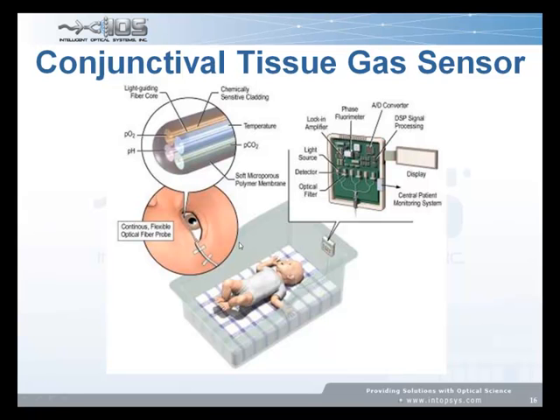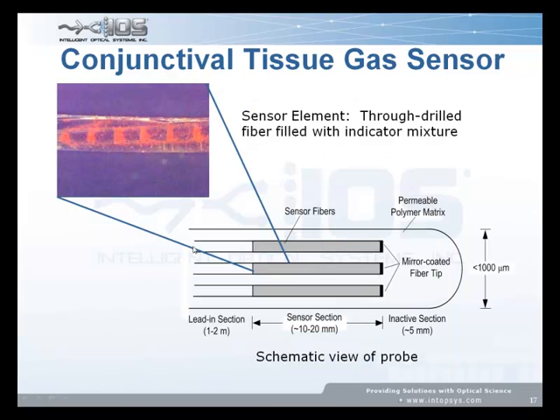We found that yes, they blink a lot, but you don't have to stick them with needles. By putting this probe in here, you can wind up making a very good real-time online measurement. You want to make it as small as you can. So in this case, instead of putting it on the tip of an optical fiber, we have actually drilled holes in the sides of optical fibers and embedded the pH, PCO2, and PO2 indicators in the fibers themselves. So you could theoretically do all 3 measurements on a single fiber. The probe that we've actually packaged and are hoping to do some clinical trials on in the next year or 2 is 3 separate fibers.